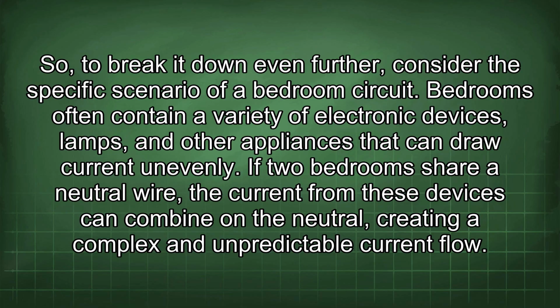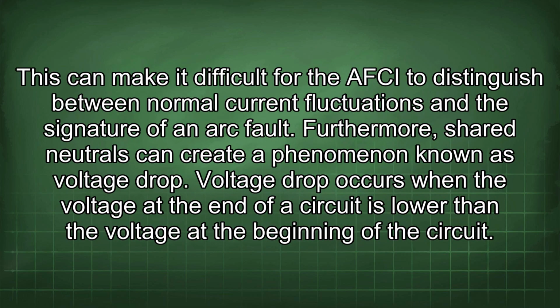So, to break it down even further, consider the specific scenario of a bedroom circuit. Bedrooms often contain a variety of electronic devices, lamps, and other appliances that can draw current unevenly. If two bedrooms share a neutral wire, the current from these devices can combine on the neutral, creating a complex and unpredictable current flow. This can make it difficult for the AFCI to distinguish between normal current fluctuations and the signature of an arc fault.